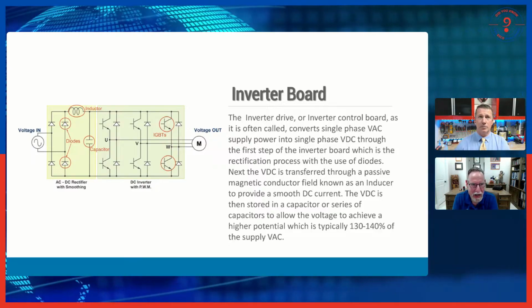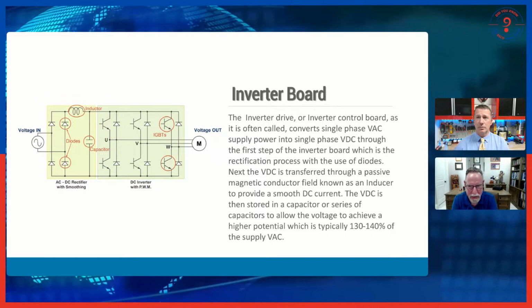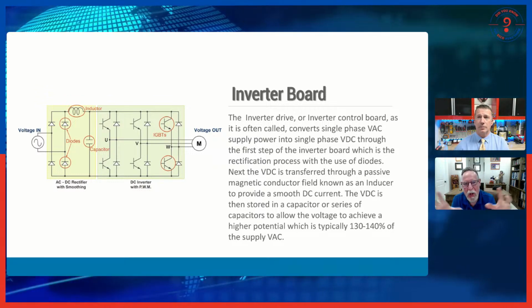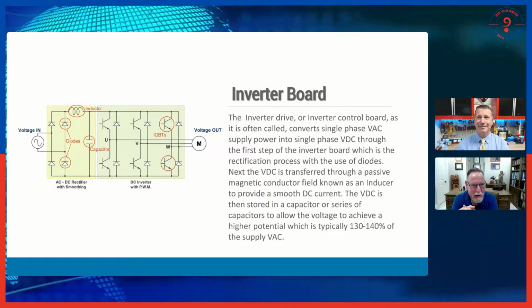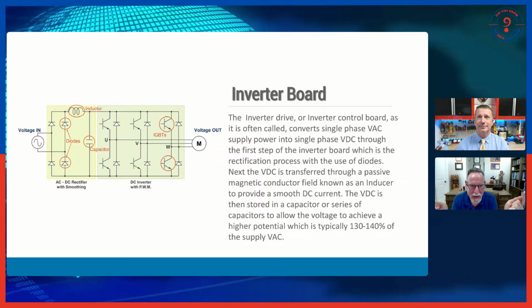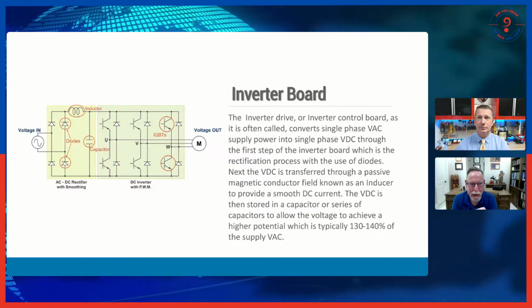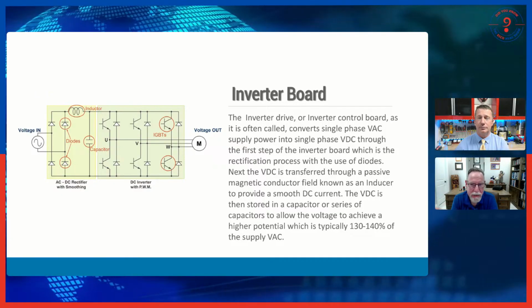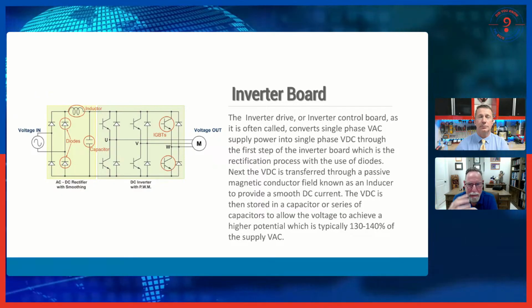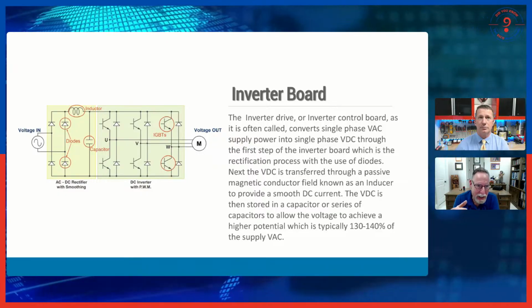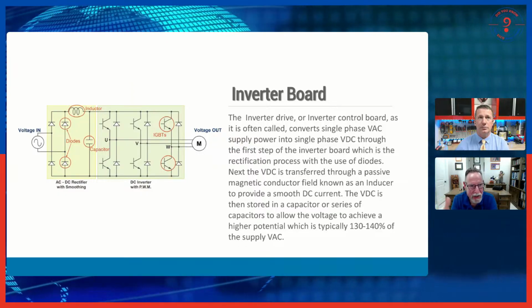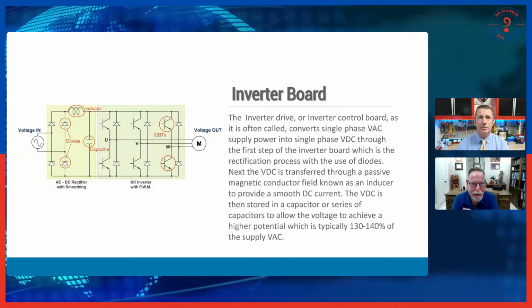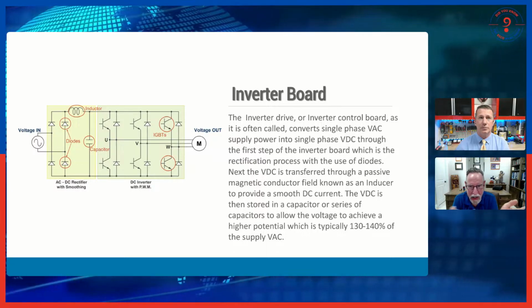There's a slide at the end of this presentation that shows all the connections on the board for all of these sensors that feed into it. Every manufacturer has different sensors, and every sensor is going to have different resistance values at different temperatures. And you might have pressure transducers that actually act as capacitors.